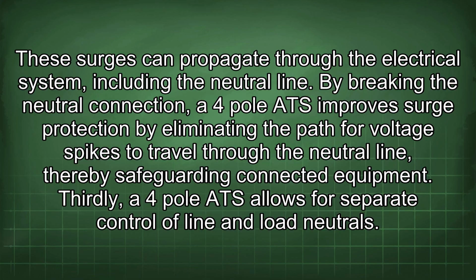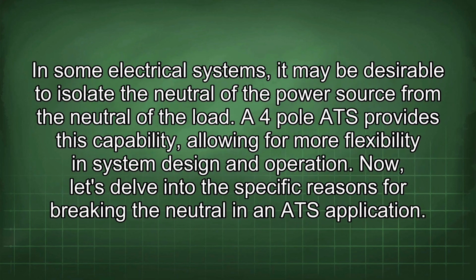Thirdly, a 4-pole ATS allows for separate control of line and load neutrals. In some electrical systems, it may be desirable to isolate the neutral of the power source from the neutral of the load. A 4-pole ATS provides this capability, allowing for more flexibility in system design and operation. Now let's delve into the specific reasons for breaking the neutral in an ATS application.